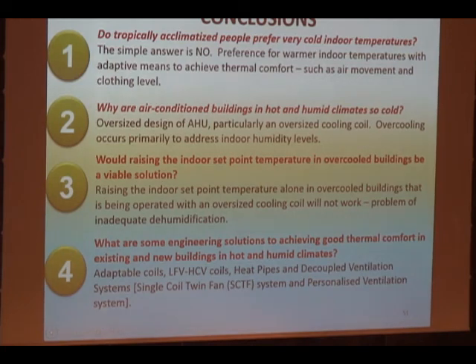Why are air-conditioned buildings in hot and humid climates so cold? We discussed this: an oversized design of the air handling unit, an oversized cooling coil, leads to an inability to dehumidify properly. Hence we overcool to pull the moisture out, and people feel cold.